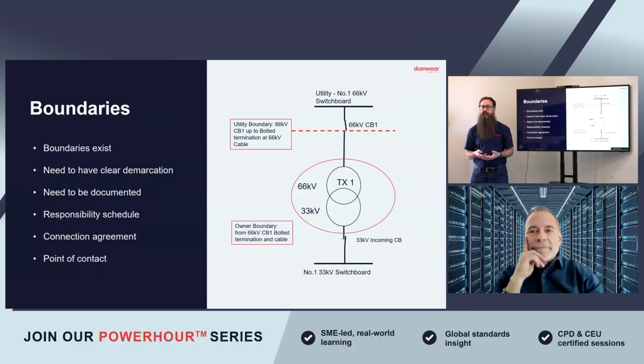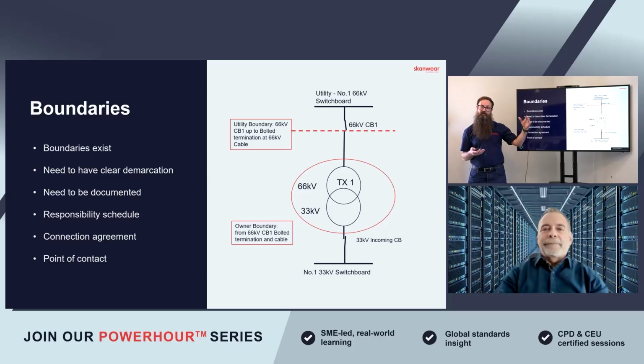In this example, we've got a utility supply, or a DNO supply if we're based in the UK - a simple supply to a site, and we've got to have clear demarcation. Here we've got a 66 kV connection to the utility provider, and we need a clear boundary point where it goes from one person's system to another. In this case, it's denoted as a 66 kV circuit breaker 1 up to the bolted termination on that cable. So it's clear that the circuit breaker itself belongs to the utility company, but the bolted connection and the cable coming onto my site - as the owner, I own that, and everything downstream, so TX1 and everything downstream is mine.